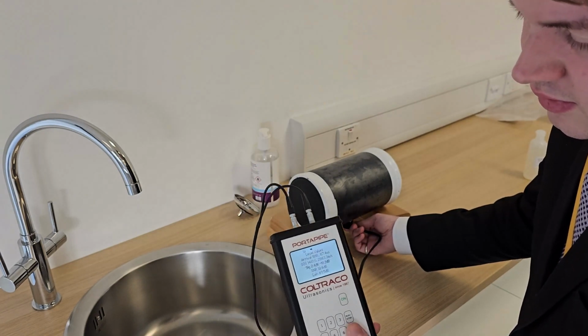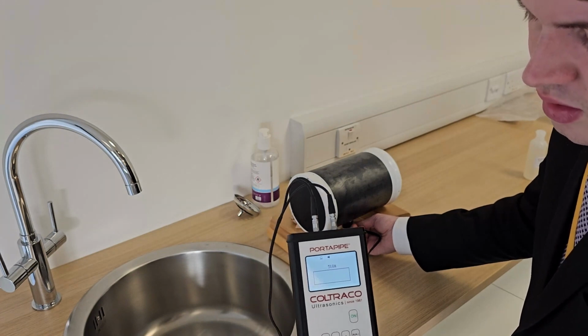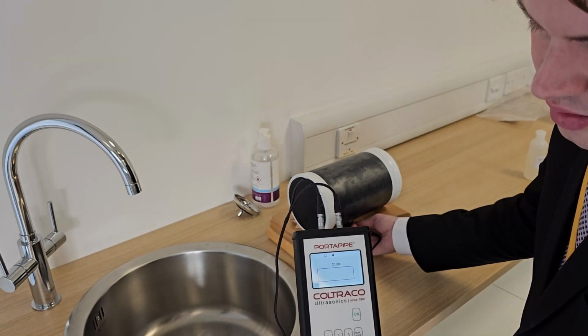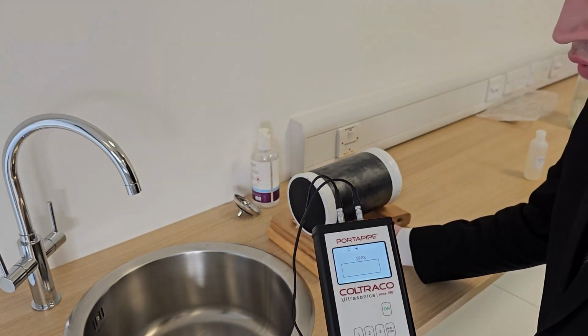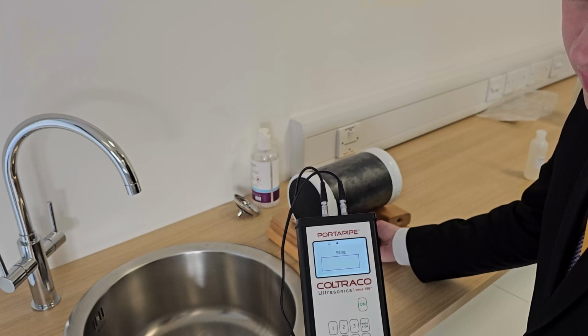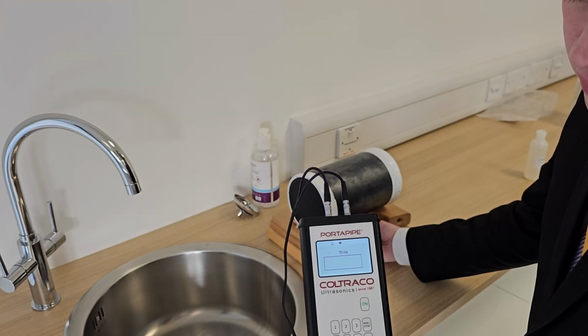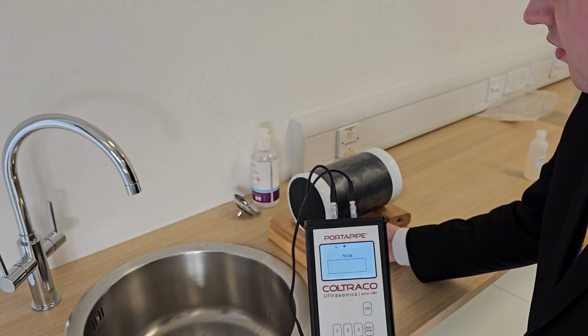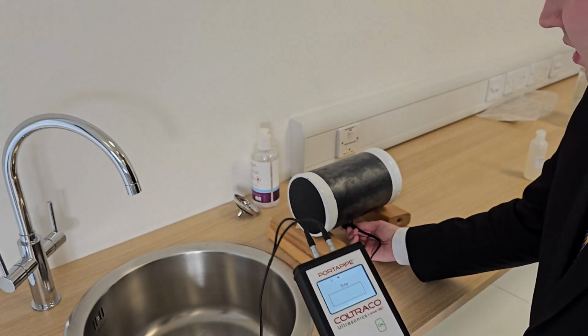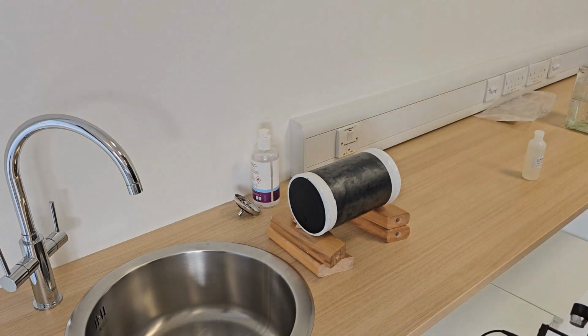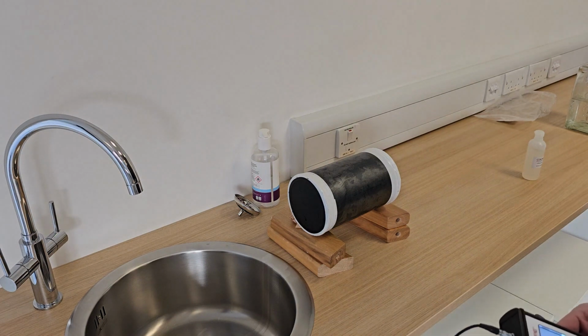So if I press Enter and go back to our percentage fill screen, we can see that we are indeed at about 51%. As I say, these readings are varying slightly. That's just because I'm moving things around slightly by accident as I'm placing this on there. But if we get that fixed into a nice place, 51% is looking about right. So as expected, we filled this about halfway, and the Portapipe is telling us we've got something like 51 or 52% filled. And that's how you would find the liquid level on a horizontal or vertical pipe using Coltraco Ultrasonics' Portapipe Ultrasonic liquid level indicator.